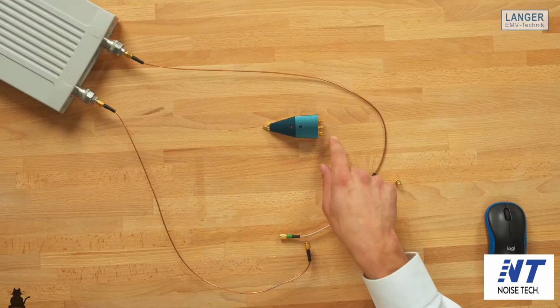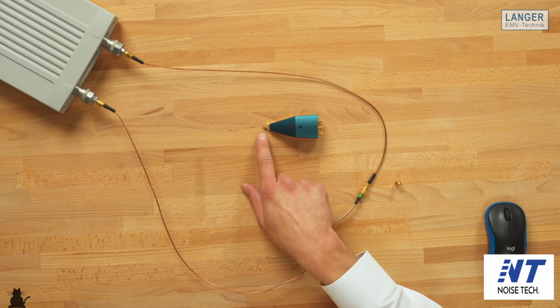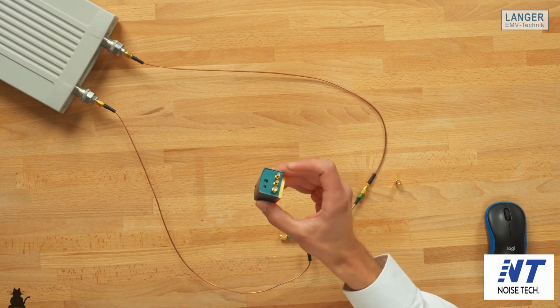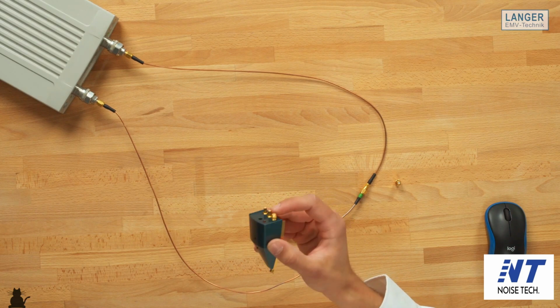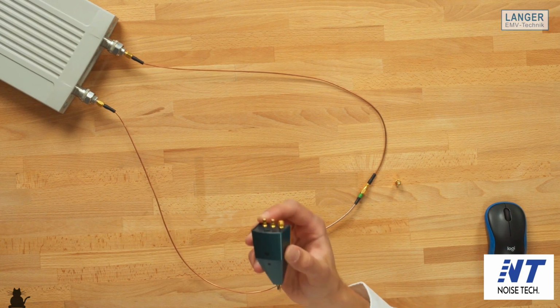So this means we need to do 3 calibrations in total today. The first one is for the transmission curve from the SMA connector to the pin contact. And the 2 other calibrations we will do is for the ampere meter and for the voltmeter.